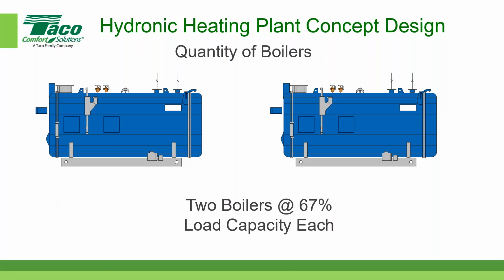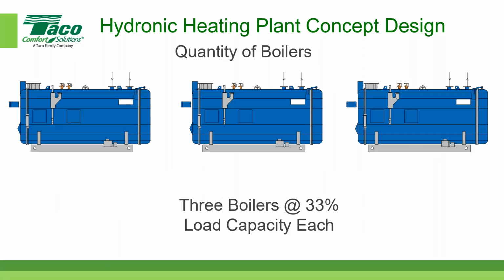And if you're in that range where it's quite cold out and you're in that upper 10 to 15% of the time where you might need more than 67% capacity, then you have 2 boilers that will be more than enough. Right. And by sizing them at 67%, you make the individual boiler more energy efficient. So that's some of the things to think about.